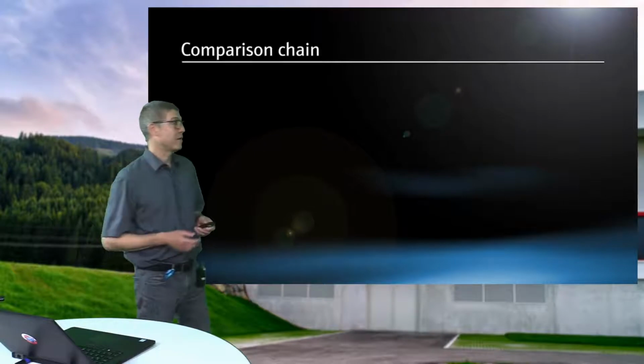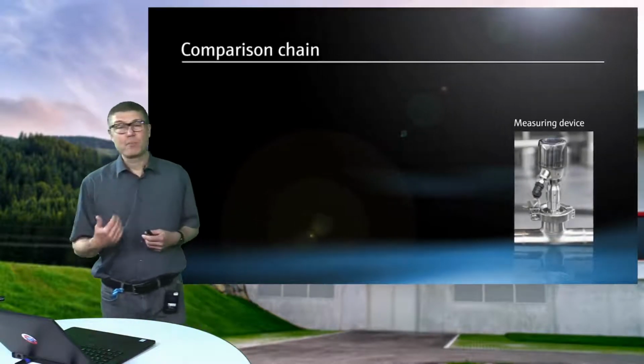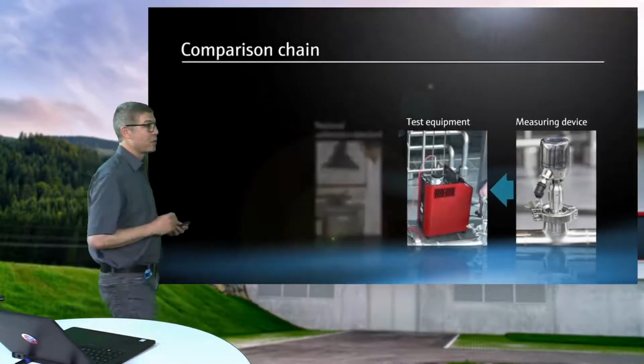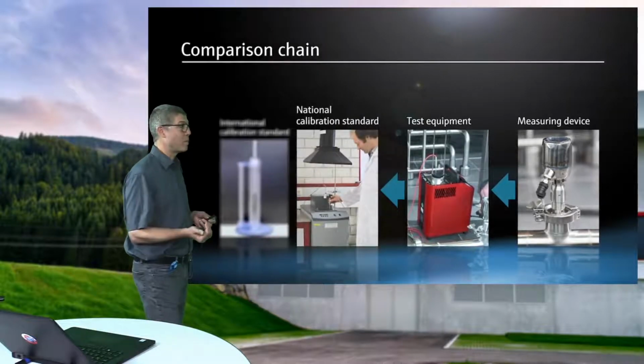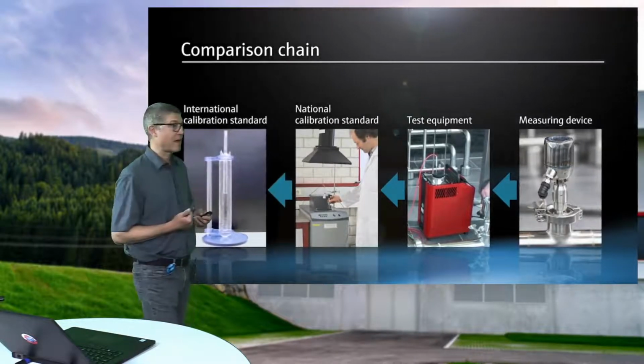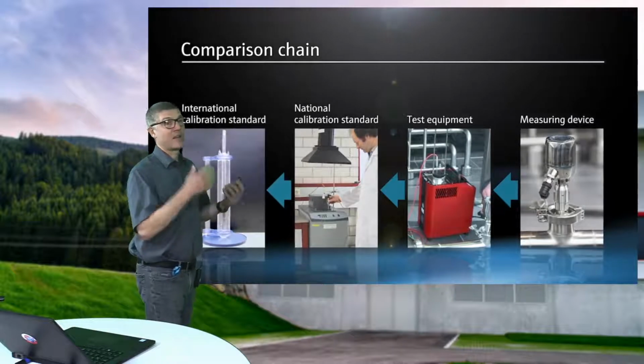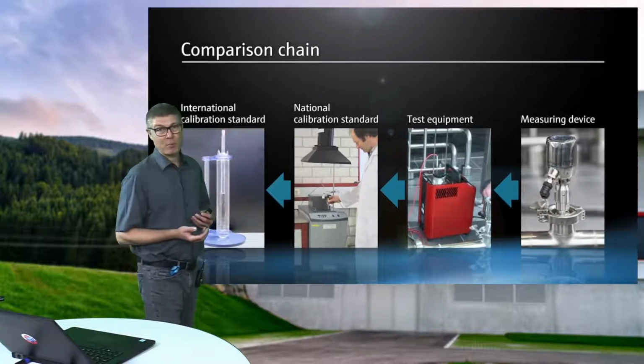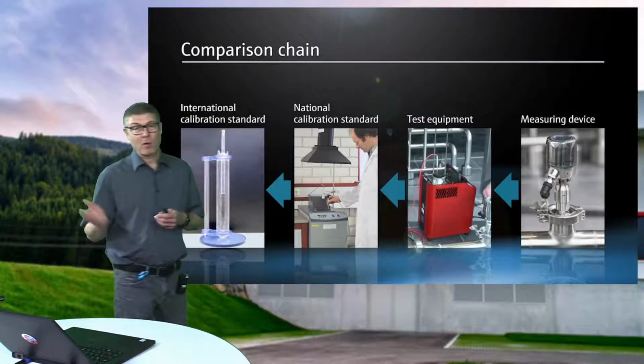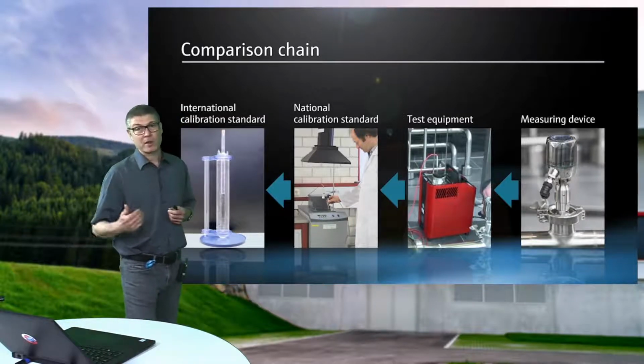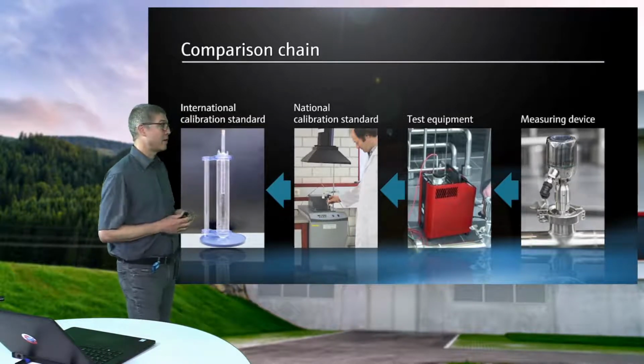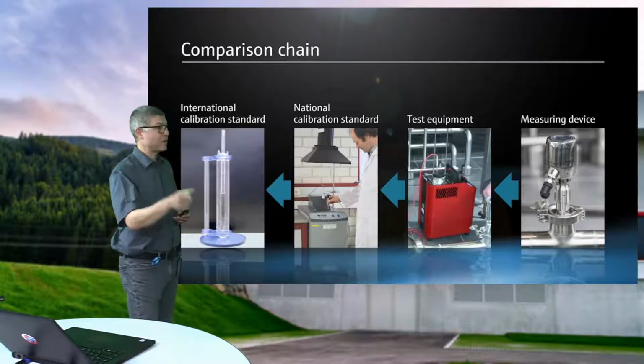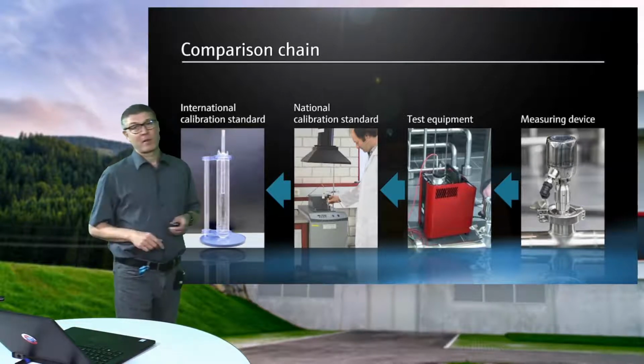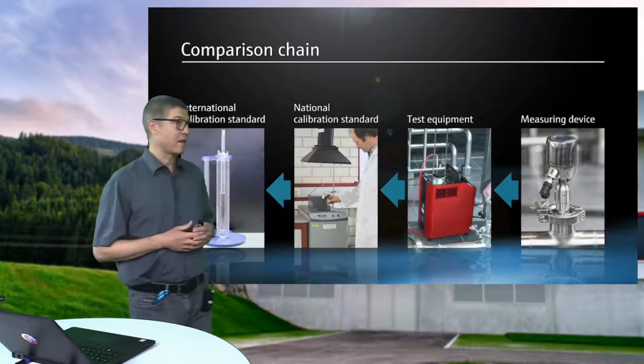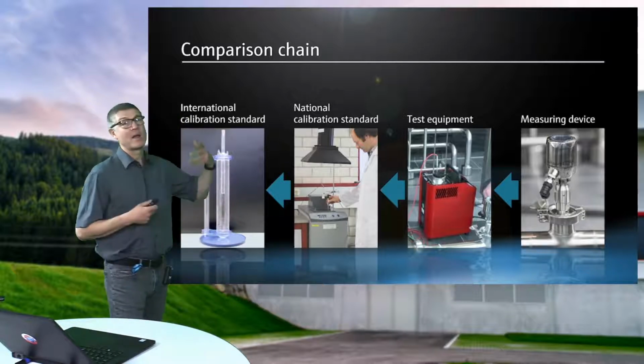And we can visualize it here, the traceability chain. We have our measuring device, we have our test equipment. The test equipment itself is calibrated in an accredited calibration lab. For example, we have one, a German accredited lab, here in our facility, and this national lab is connected to an international standard.